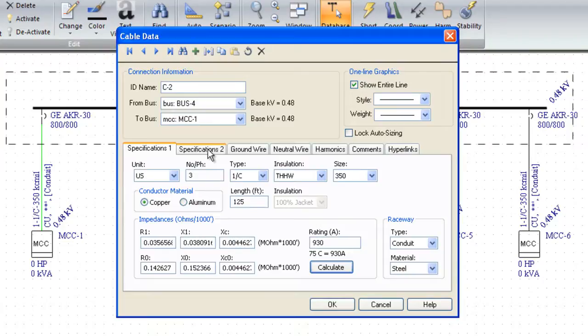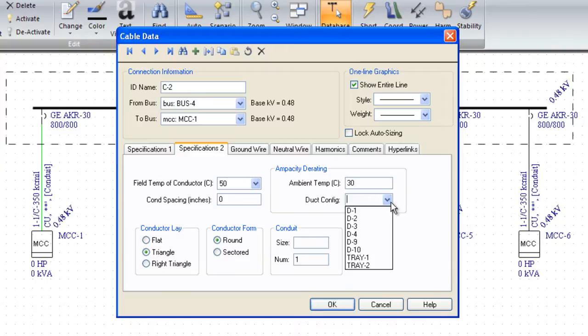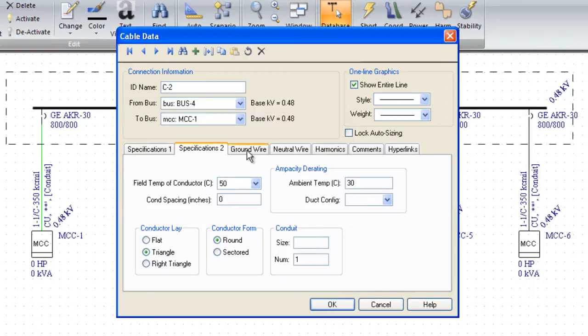We can get really fancy if you want to go into specifications and model different duct banks and tray derating, whether the conductor is flat triangular or right triangular, what the conductor spacing is, and any field temperatures and things. You typically do not need to do that for most studies.